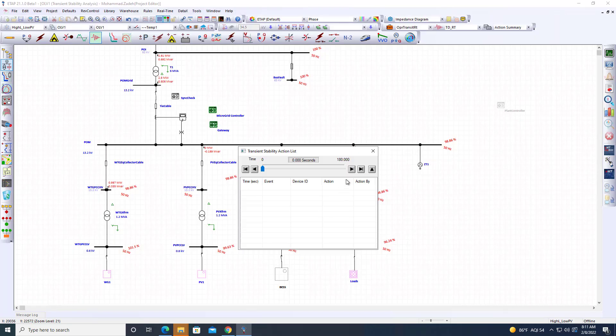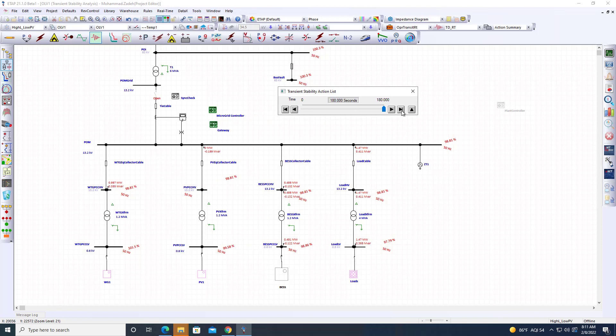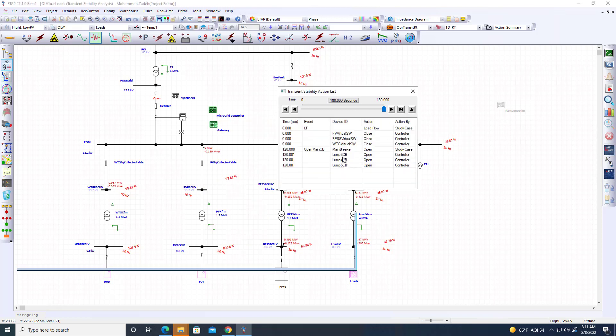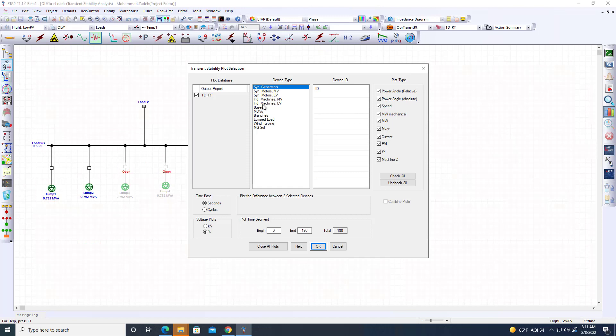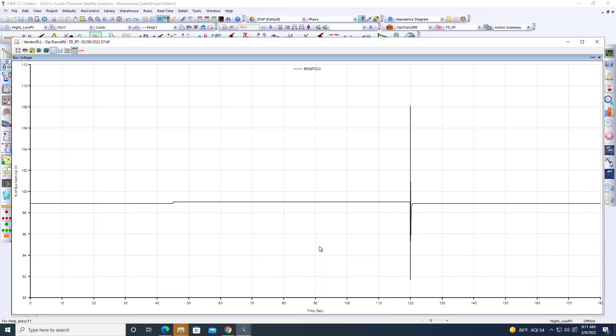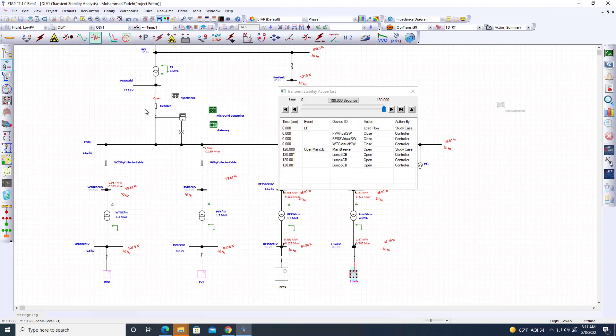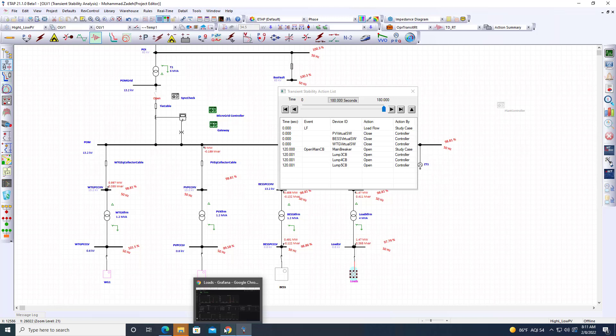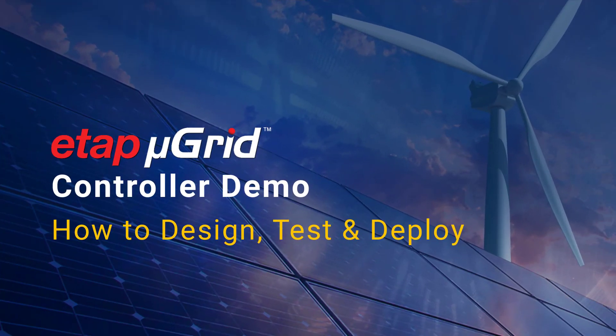Now let's go back. Simulation is done. We just ran for three minutes, and let's look at the performance of the system here. We did the three load sheddings, and if I go and plot the bus voltage, if you remember the simulations, we exactly get the similar performance. System comes back to normal. With that, we show that actually how nicely you can use ETAP as a real-time digital simulator, and how easy it is that from the software simulation go all the way to the hardware simulation. Thank you for your attention.